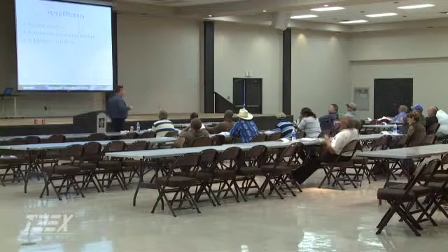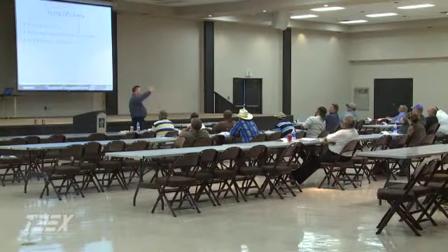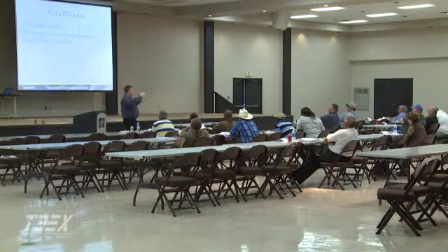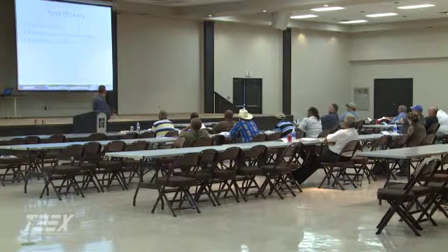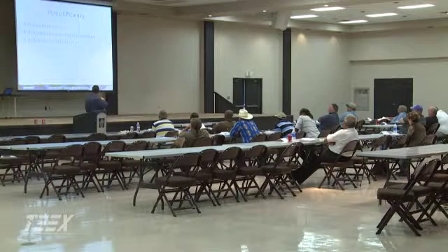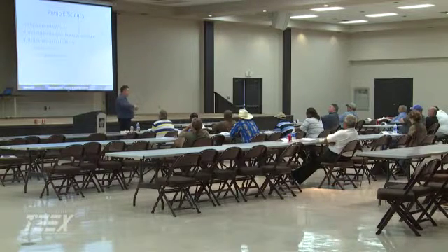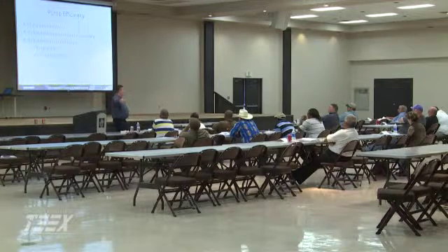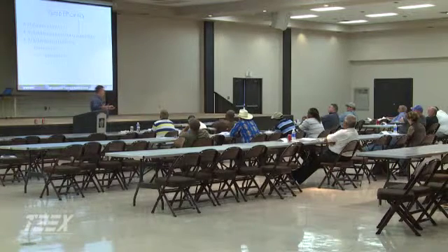As your head increases, remember, the head is a force you're working against. So as you get more head, your efficiency reduces because you're trying to fight against more friction, more force pushing back against you. So your pump's going to become less efficient. Also, if you have a high suction lift, that's going to reduce your efficiency. A worn or clogged impeller. Remember, that impeller takes that water, spins it around, creates that centrifugal force pushing it out the side. Well, as that impeller wears, it's going to become less efficient.